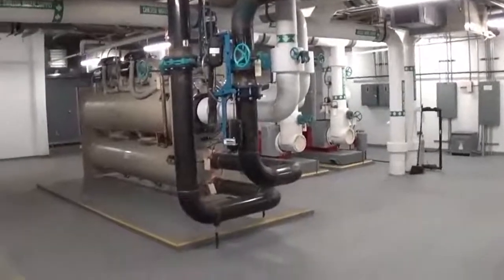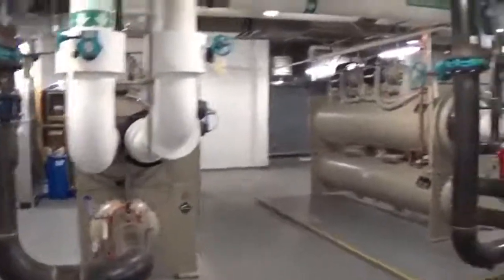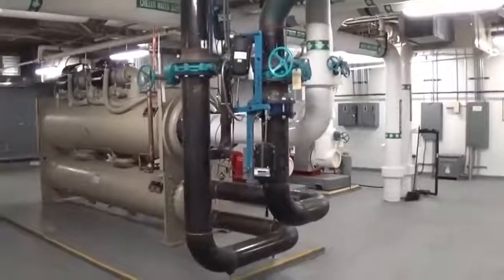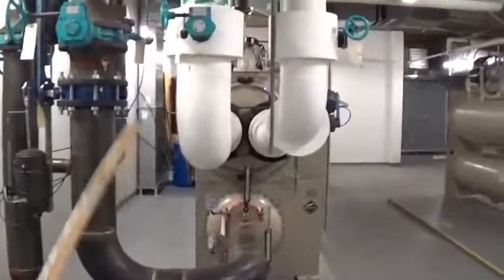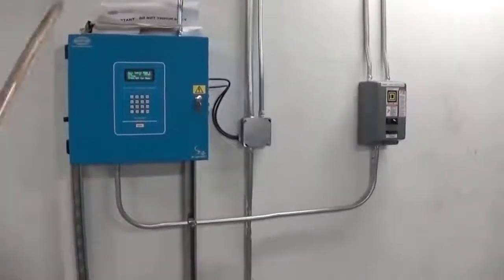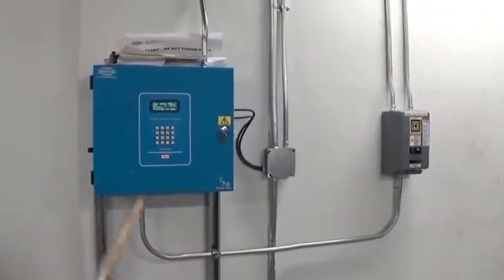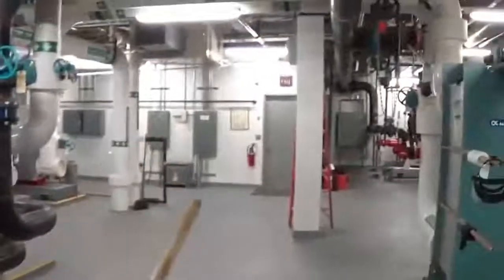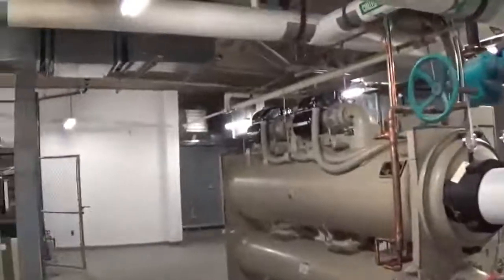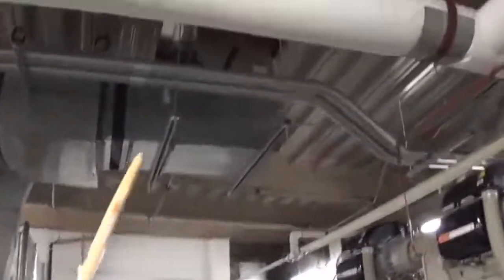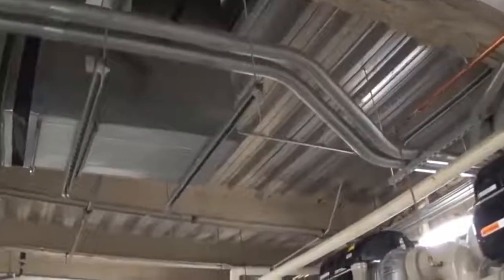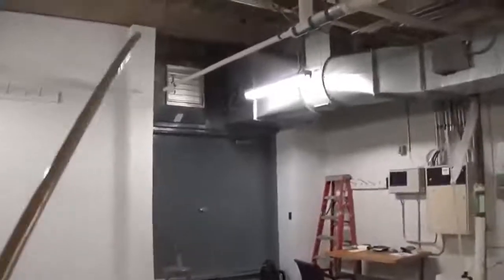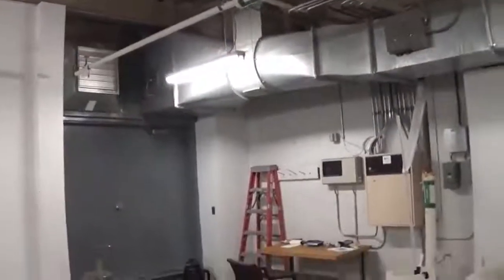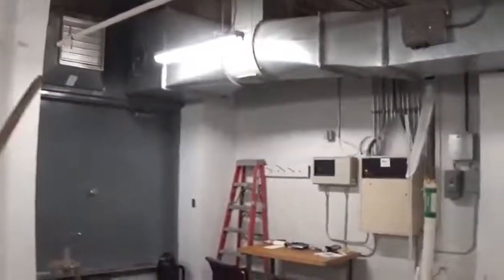Because these are new chillers, they do use a new refrigerant, which is not a happy chemical, and it is toxic, as opposed to the R11 refrigerant, which was an ozone killer, but it was not deadly. So if we have a catastrophic failure here and a refrigerant leak, we do have a sophisticated detector here, which is constantly sampling the air for any issues. It will lock down this chiller plant so that no one can enter. And over here, it will turn an emergency fan on, which will evacuate the air up through and out to the atmosphere. It will also take in a bundle of fresh air through this system here, and of course replenish the bad stuff with fresh air.